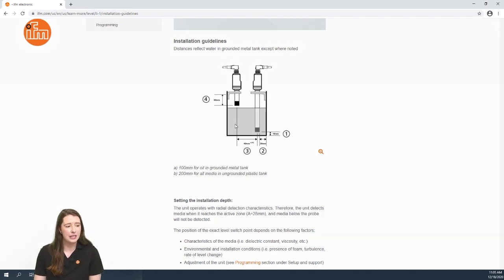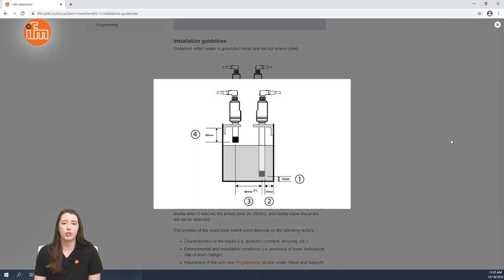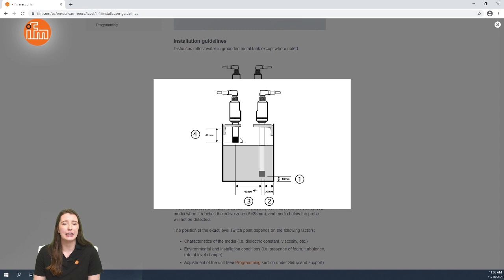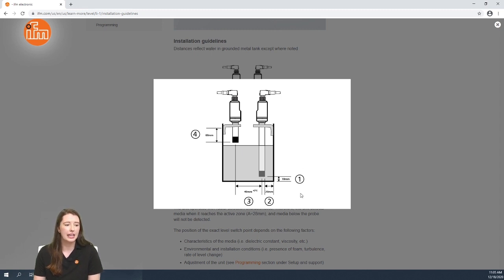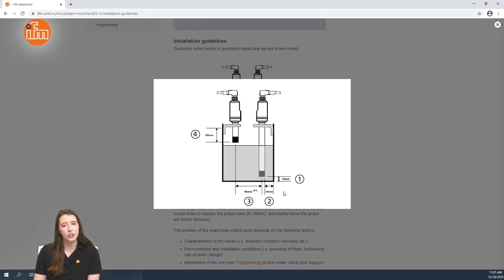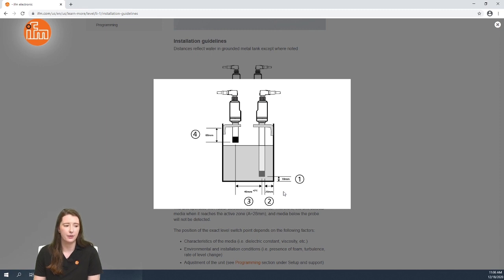In this image we go over the required positioning of these sensors in a tank application. First the probe must be at least 60 millimeters below the mounting connection or inside of the tank wall. Second the probe must be at least 10 millimeters away from the bottom of the tank and 20 millimeters away from the inside of the tank.